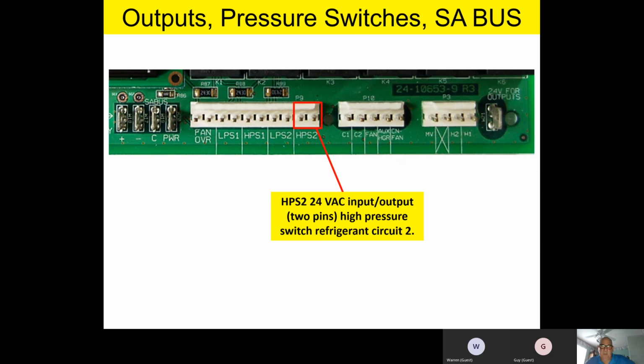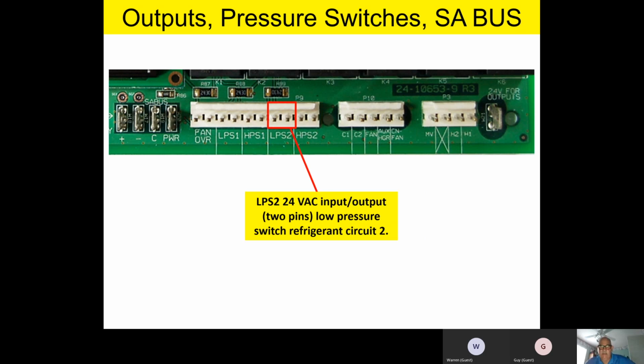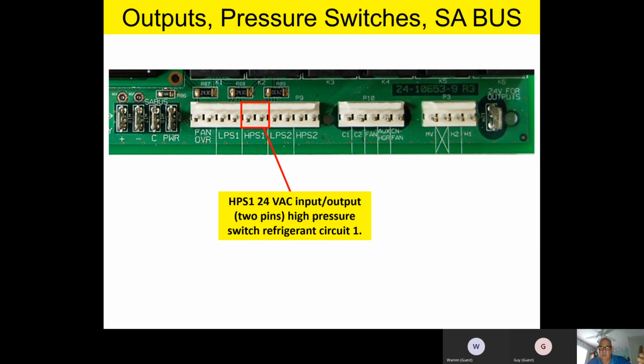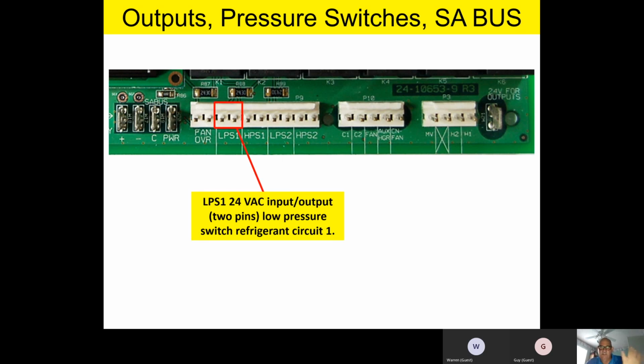As we move to the left of all that, we see we've got some HPS2 and LPS2. This is where your pressure switches hook in. These are your safety pressure switches, your high pressure switch and a low pressure switch. And again, if you've got multi-stage equipment, you'll have more than one of these hooked up. So basically, if it's a single stage piece of equipment, you'll just have HPS1 and LPS1 hooked up. For low pressure switch and high pressure switches, this is your refrigeration safety circuits.